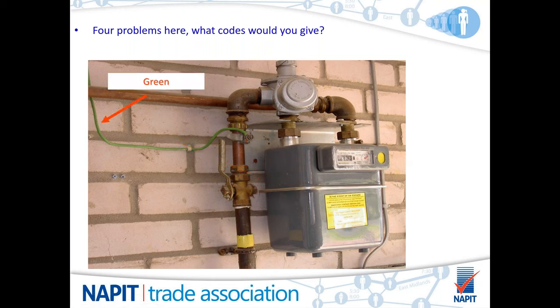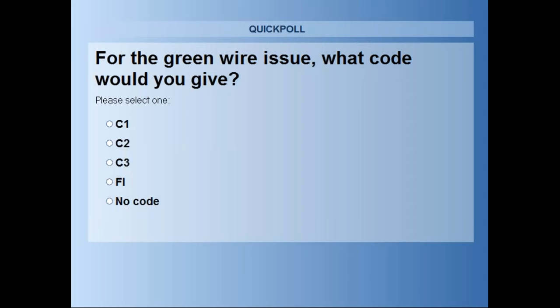And the last one, it's obviously that the protective conductor was installed long before the new colour codes came out, and it is only a green colour, not a green and yellow. So again, just a quick opinion on what your codes would be. Great, thanks, Paul. The final poll for the evening is, what code, if any, would you give to the incorrect colour of the protective bonding conductor? Give you a couple more seconds to give us your codes for this. Great, I'll close that one down.